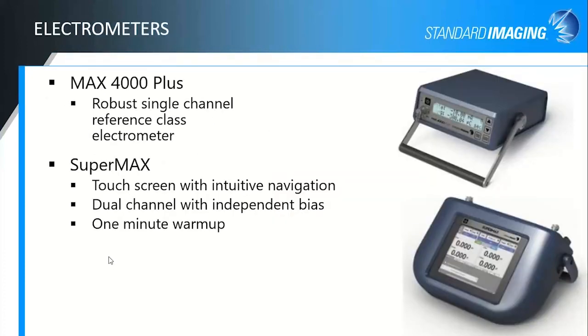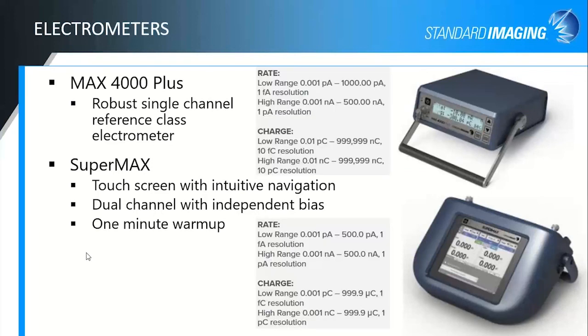I'd be a little remiss in talking about small fields without bringing up our electrometers. I mentioned that you need to have something that is accurate and sensitive enough for the measurements you're making. We have two that I'd like to point out to you today if you're not familiar with them. The Max 4000 Plus is a workhorse. It is a fabulous electrometer that's going to last you years. It's just a single channel reference class electrometer, but it has a wide range that it can be used both for current, low and high range currents, as well as charge collections.